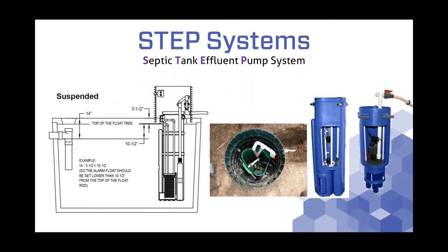STEP systems are typically what we'll use, installed inside a separate pump tank or sometimes a two-compartment septic tank. We install these rotomolded plastic vaults — typically 60 inches in height, but available in various heights depending on the pump tank depth. They're installed and hung on the inside of the pump tank, as you can see in the cross-section on the left. The key feature is a turbine pump inside; sometimes a centrifugal pump depending on the version.